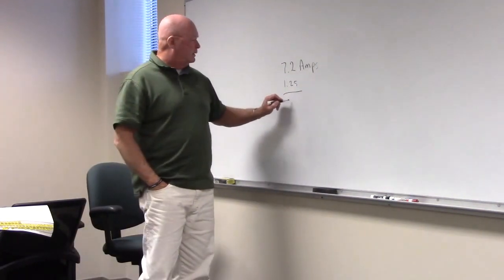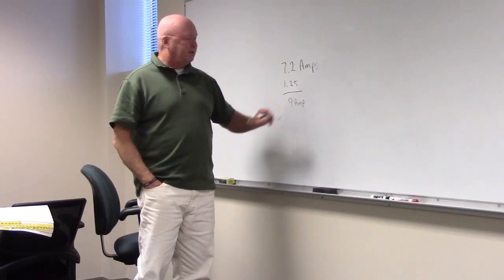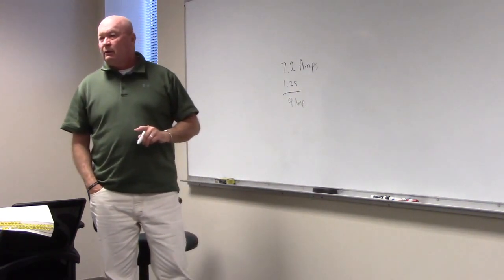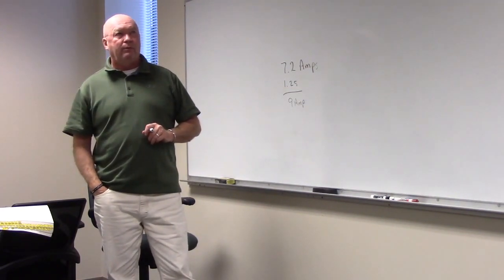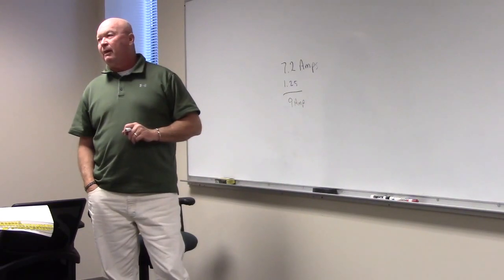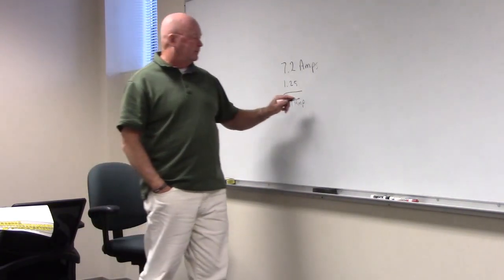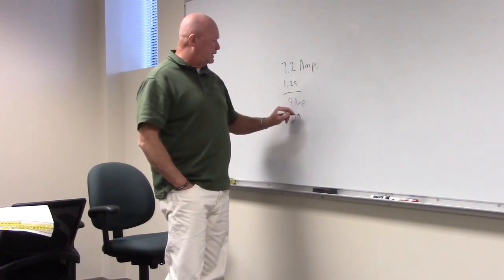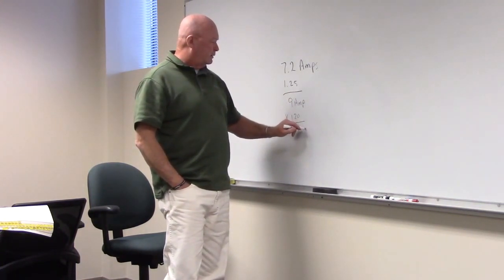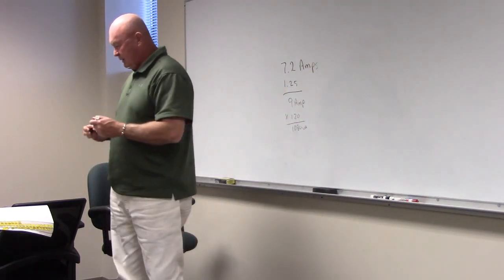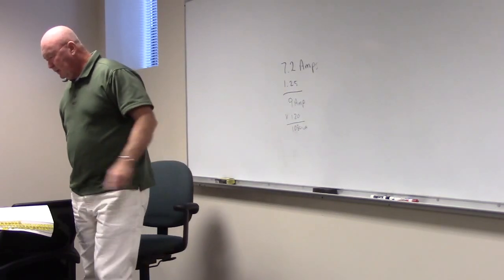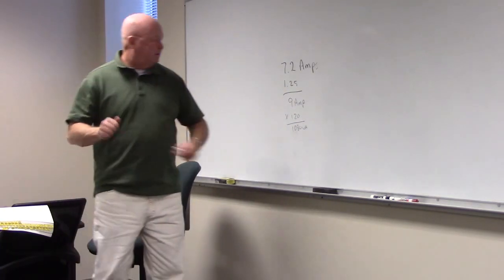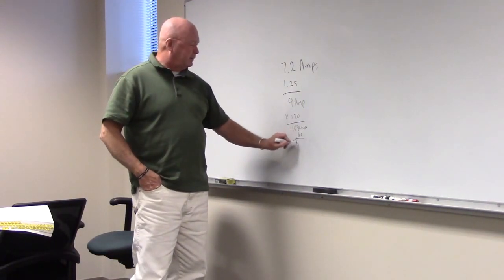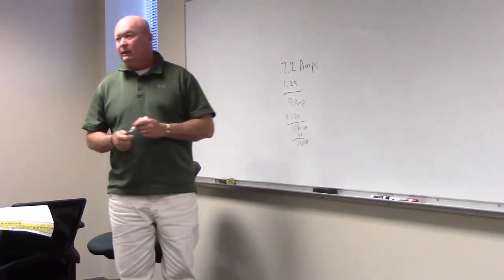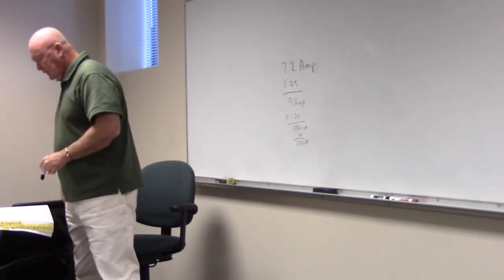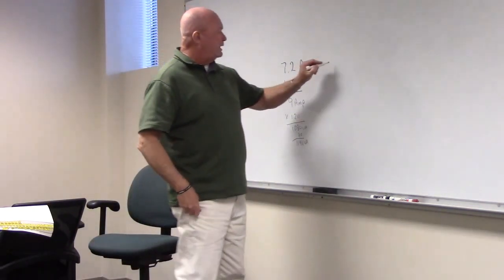So tell me how much that is. Yeah, 9 amps. We want to get the volt amps. What's our voltage? 115 or 120? 120. Very good. So 9 times 120 is how much? Like 1,080 volt amps? Is that right? Okay, so 1,080 volt amps. Now we've got our 60 watt bulb we're going to put on there. And that's going to give us what? 1,140 volt amps. Okay. If you look there, that's what it says so far. So we've got 1,140 volt amps total.